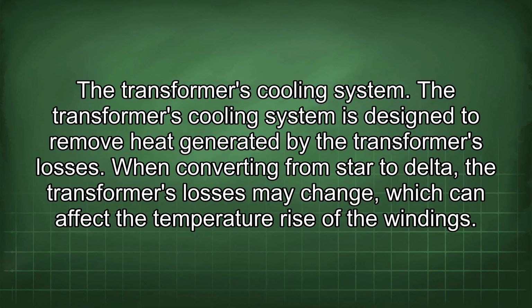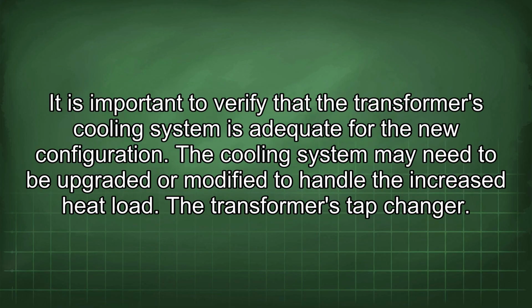The transformer's cooling system. The transformer's cooling system is designed to remove heat generated by the transformer's losses. When converting from star to delta, the transformer's losses may change, which can affect the temperature rise of the windings. It is important to verify that the transformer's cooling system is adequate for the new configuration. The cooling system may need to be upgraded or modified to handle the increased heat load.